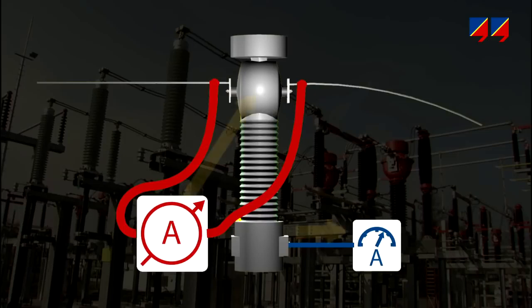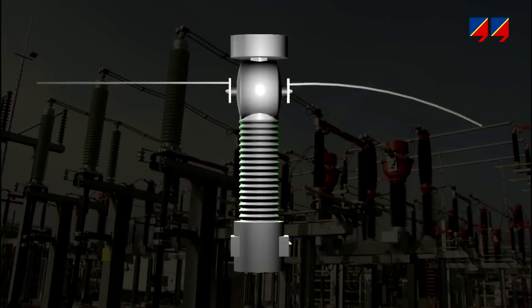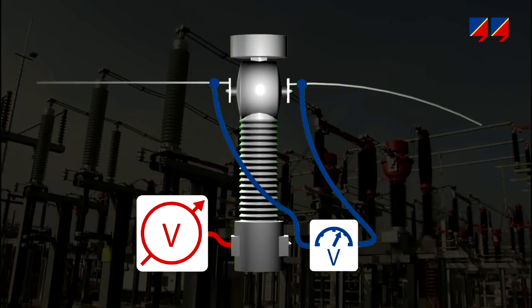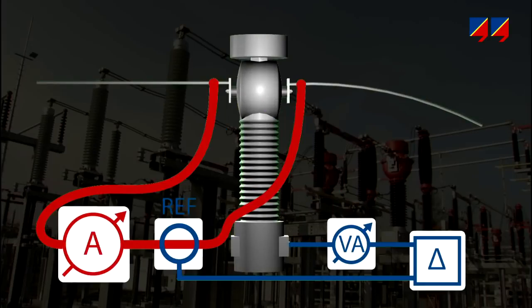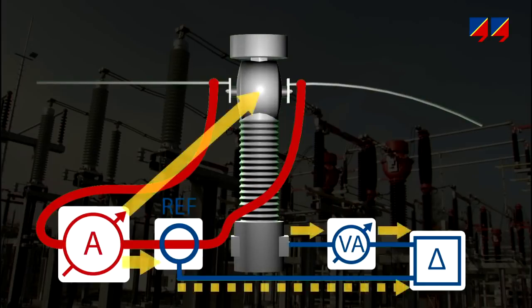The three methods are: primary current injection using a portable high-current source; secondary voltage injection using a portable variac; and primary nominal current injection using a high-current source, a reference CT, a burden simulator, and a bridge.